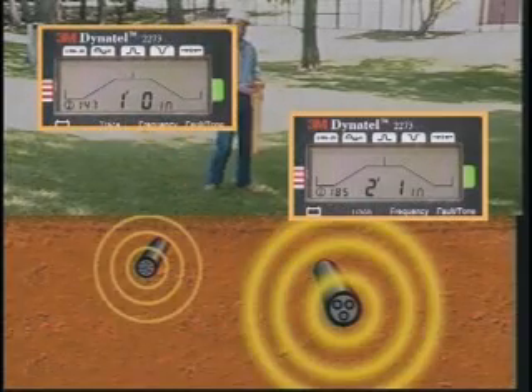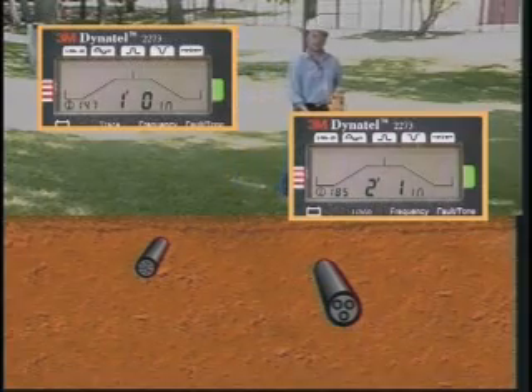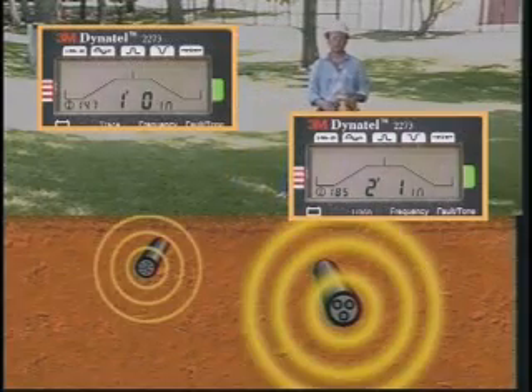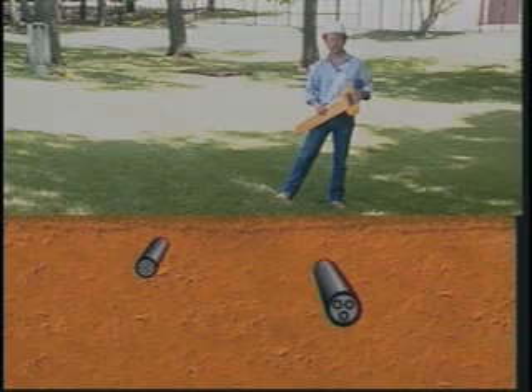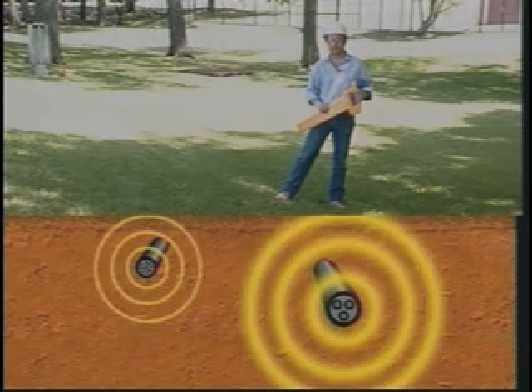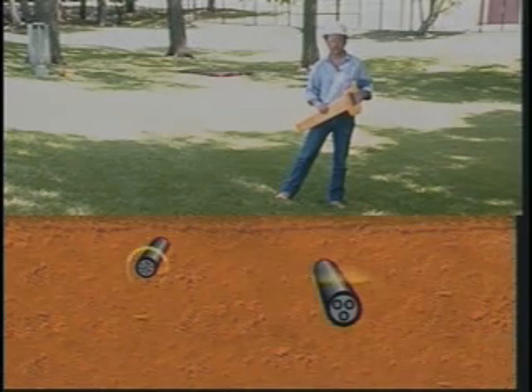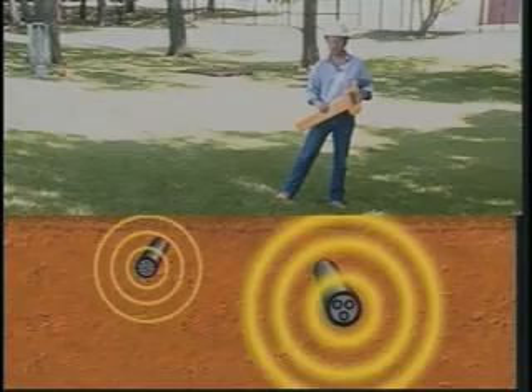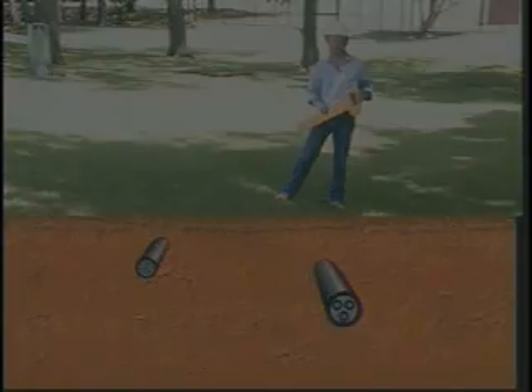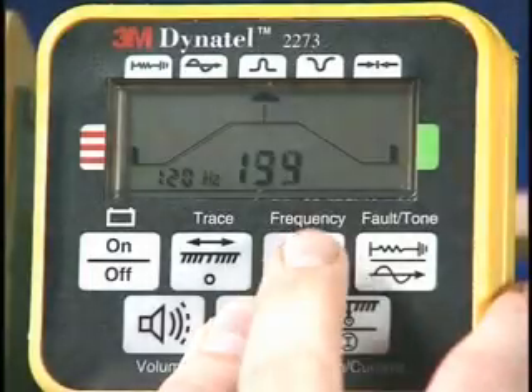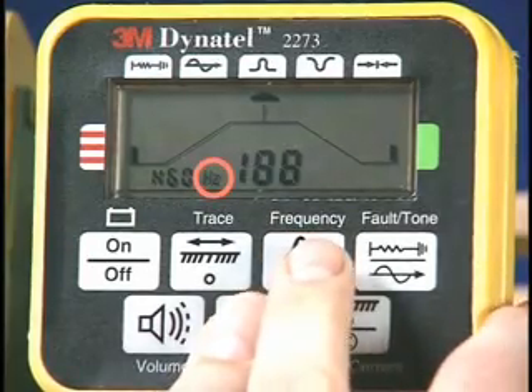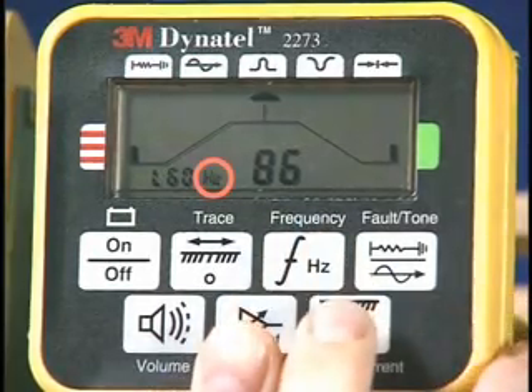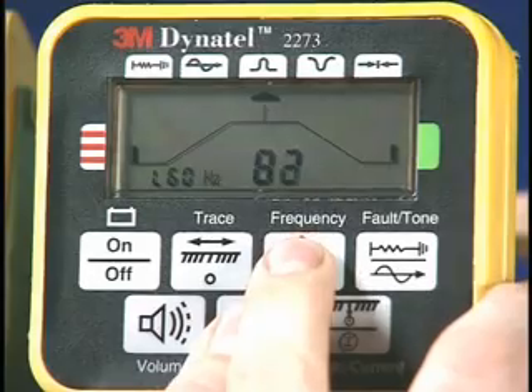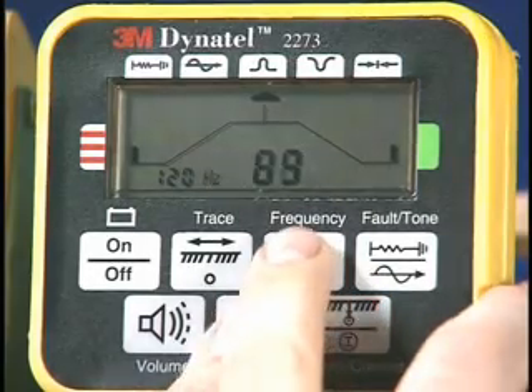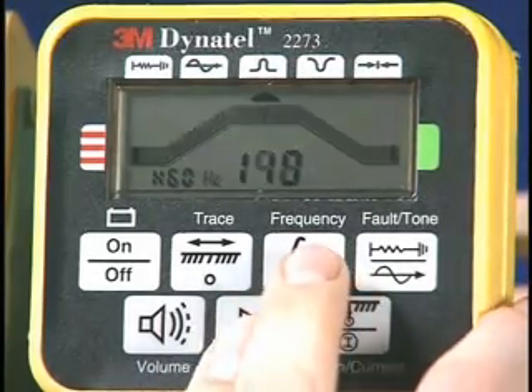As you can see, the deeper cable has the highest current and is the target cable. To reduce the possibility that the trace signal will get onto other cables, use the direct connect method at 577 Hz with good far-end ground. In newer models, the flashing Hertz symbol indicates alternate frequencies are available. To change to an alternate frequency, press and hold the gain key while pressing the frequency key.